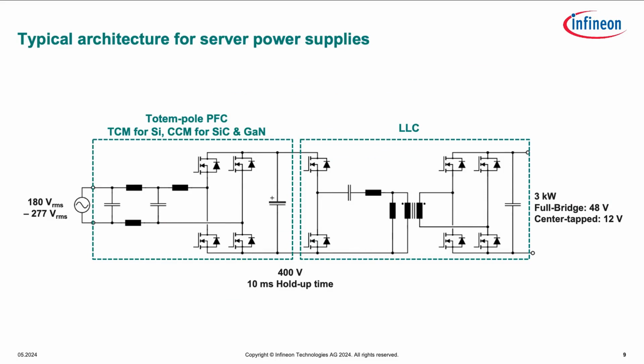The typical architecture for a server power supply consists of a power factor correction stage, followed by an isolating DC-DC stage. In the power factor correction stage, we are seeing coexistence of several topologies and control algorithms. We're seeing a big portion of the market moving into the totem pole. Within the totem pole, we see hard switching, but also soft switching applications, so-called triangular current mode modulation, which would be suitable for silicon superjunction, but which would also create a lot of benefit if taken into very high frequency applications with gallium nitride. In continuous current modes or hard switching at typically low frequencies, 40 to 60 kilohertz, we are seeing primarily silicon carbide.